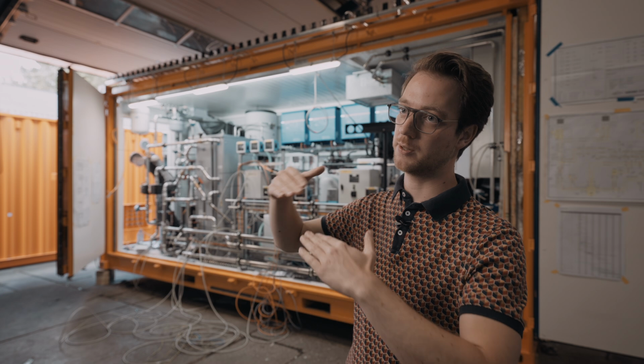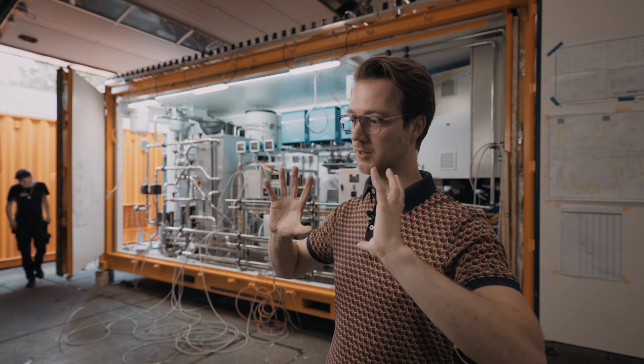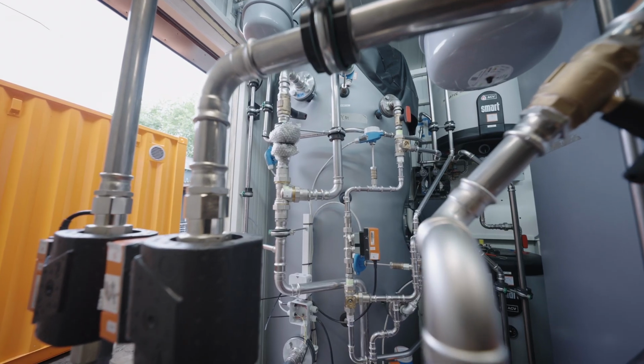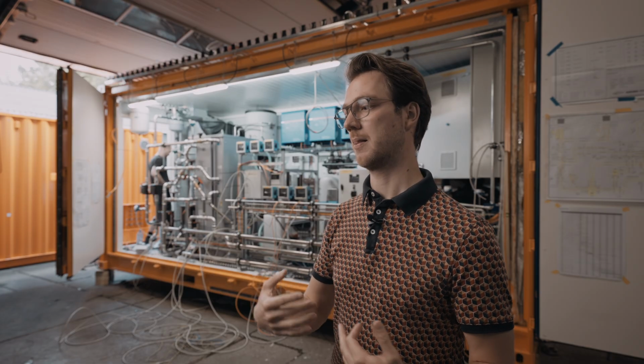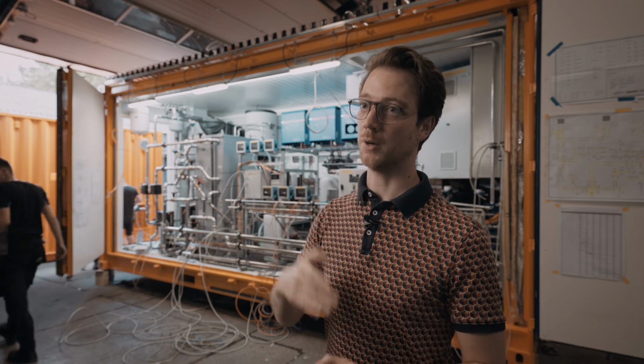And that means that as soon as we hit that phase transition point at 78, all the heat that goes into the phase change vat, instead of heating everything up, just melts the material. And it keeps storing that energy until all the salt has been liquefied, has melted. So it's very useful storage because we have that fixed temperature, but also in terms of energy capacity per weight and volume, it's far more efficient than using water would be.